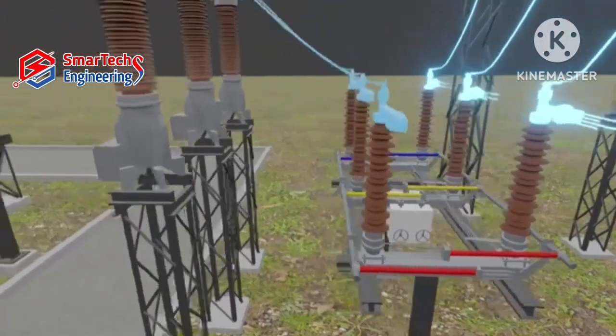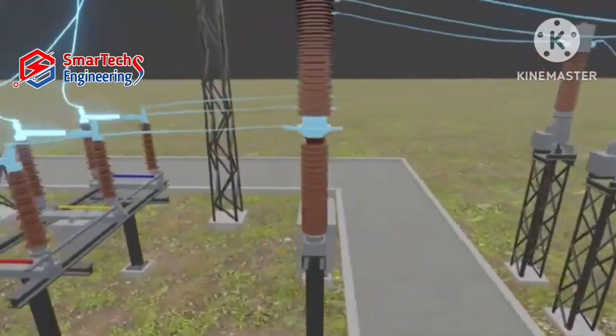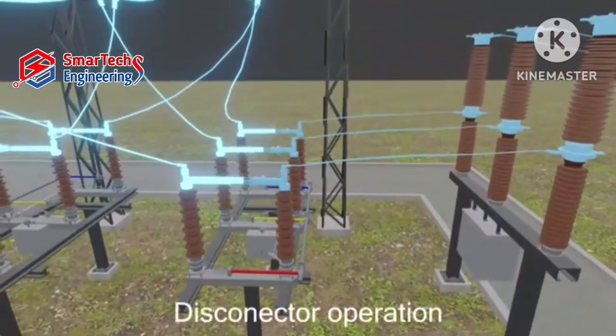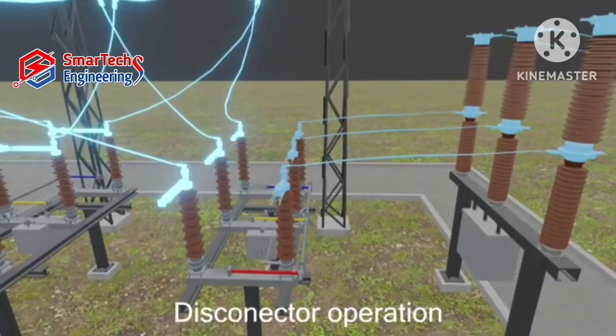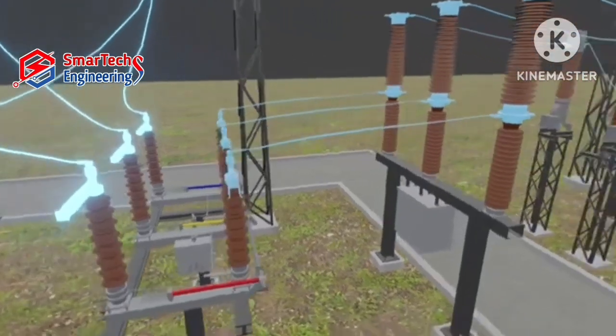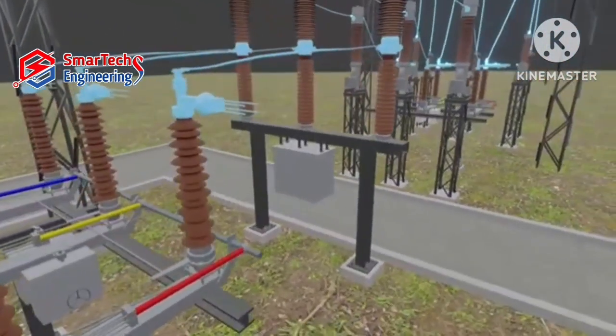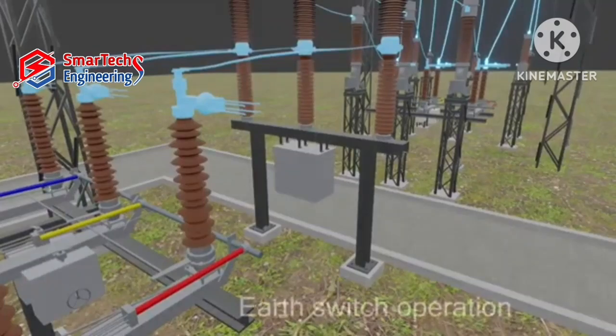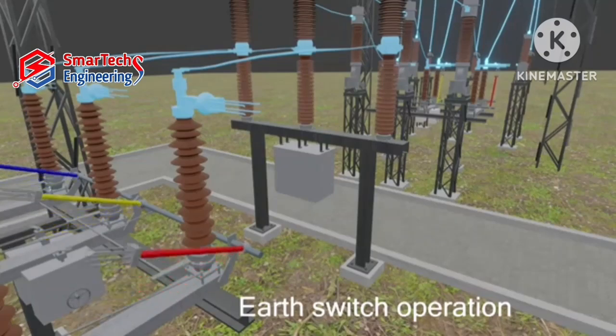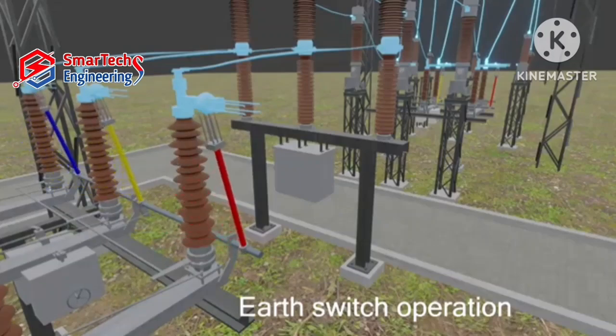When the disconnector switch operates, a heavy electric arc is produced in it. Now you can see the other side of the disconnector switch operation. After the disconnector switch is opened, we operate the earth switch. The earth switch operation is to earth or ground the residual line voltages safely. You can see here the earth switch operation for each line: red, yellow, blue.